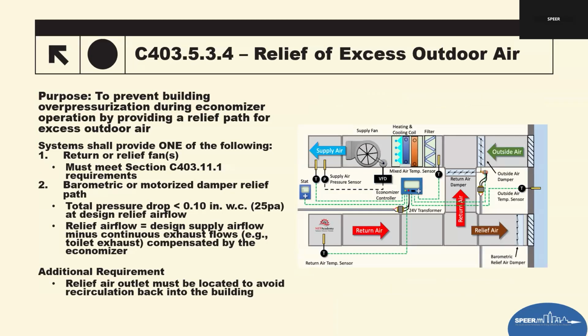So relief of excess outdoor air. So under the air economizer sections, C403.5.3.4 covers how buildings must relieve excess outdoor air during economizer operations. So economizers bring large quantities of outdoor air for free cooling, but they can create overpressurization of the building, and we want to make sure that doesn't happen by adding adequate relief path.